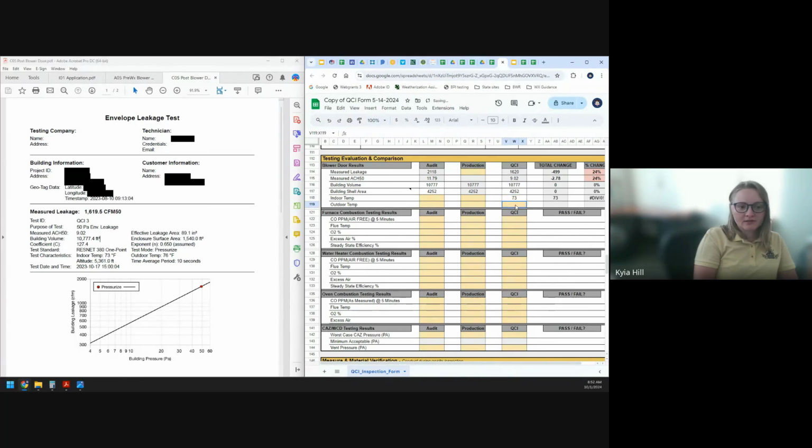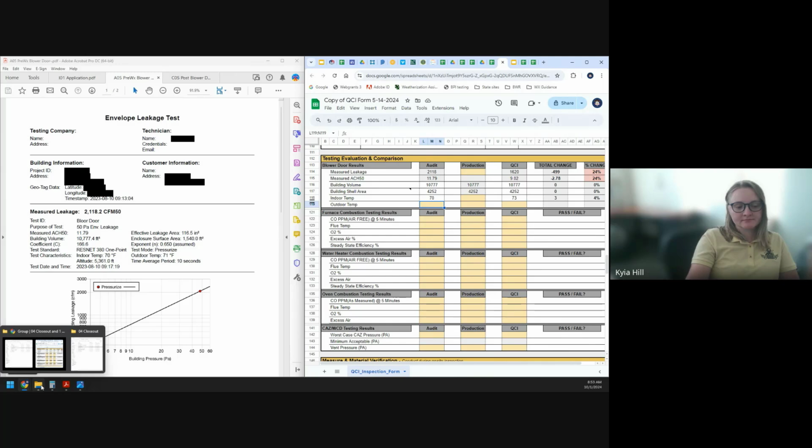That way you know if they're within that 10% accuracy, because it is possible for you to have a different building volume. And also, if there's vaulted ceilings, measure the ceiling height. Make sure that they measured the ceiling height correctly, because that's probably one of the biggest things in volume issues, when they don't correctly calculate if there's a vaulted ceiling. So we're not necessarily saying you got to do the whole thing, but if you notice that one of the walls is off, you should probably go measure a few more walls to make sure that it's not crazy off, or there needs to be a recalculation.